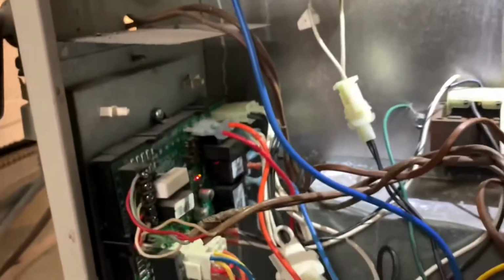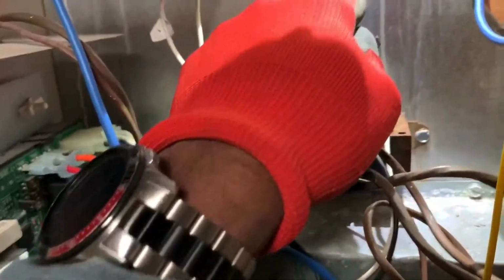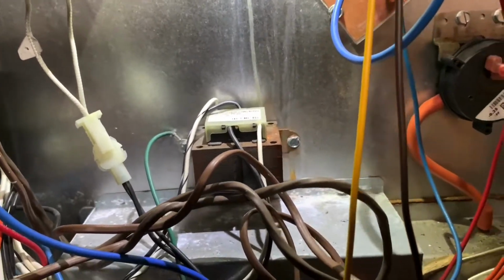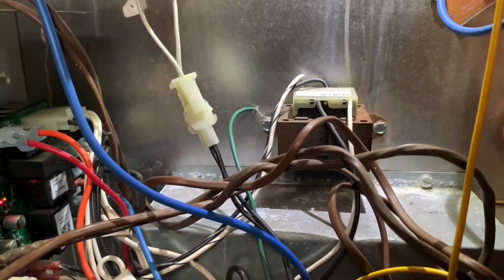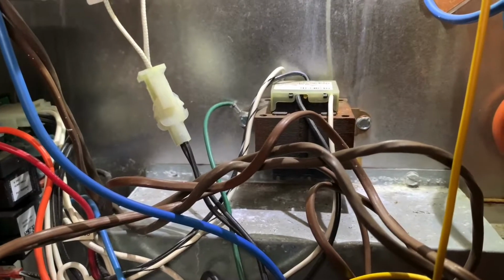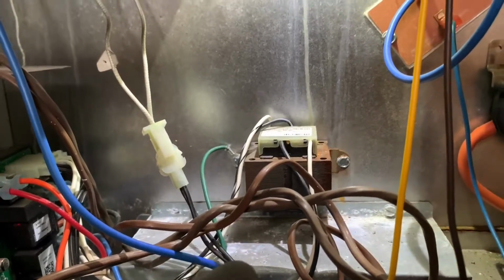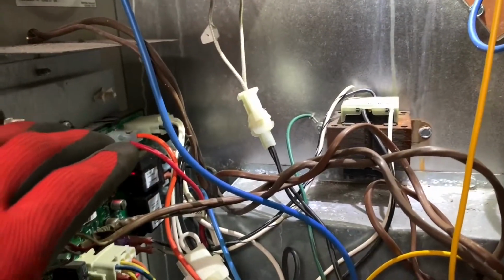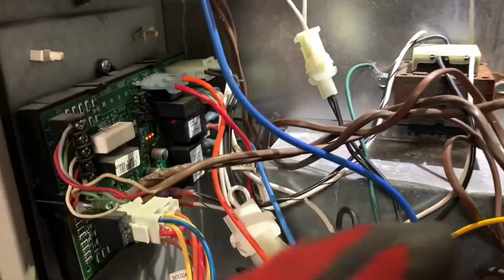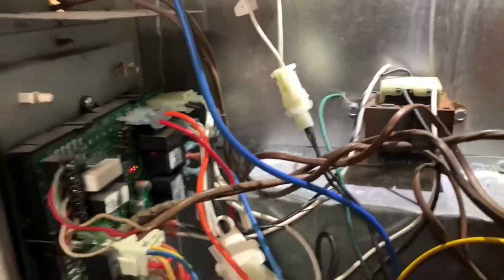Right, because the sensor is touching the flame, so it sends the signal through the flame and back to the chassis ground, right? Because remember, the fire is touching the chamber, the heat exchanger, and so the current is a small current flow, or current draw, or voltage drop, whatever you scientists want to use. It goes back to ground, and that load back to the control logic lets the control logic know there is fire in the flames. Now the problem is, and there's a tip, right?